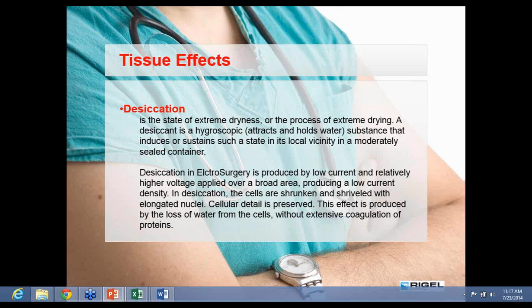And that carbonized tissue actually causes an insulation barrier. So that thin layer of carbon and desiccated tissue beneath form an insulating barrier, decreasing the probability of subsequent arc strikes on the same location. That's important for a surgeon. What's important to remember with fulguration is its low amperage and high voltage to overcome the resistance of the large distances between the electrode and the tissue, because the monopolar pencil is actually held above the tissue.